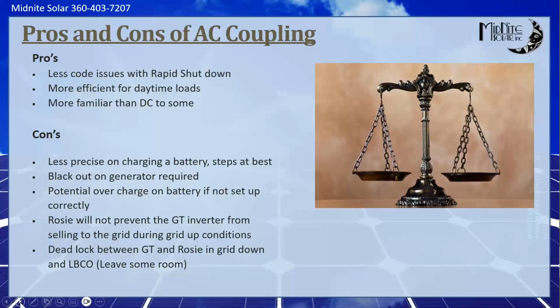So as that battery starts to fill, it can slowly step down, 1/10 of an amp at a time, 1 amp at a time, whatever that may be, until the battery is full and it can properly charge that battery, which is super important on a lead acid battery. Not so important if it's a lithium as such, and also not so important if it's a battery backup system. So we'll talk a little bit more about that.